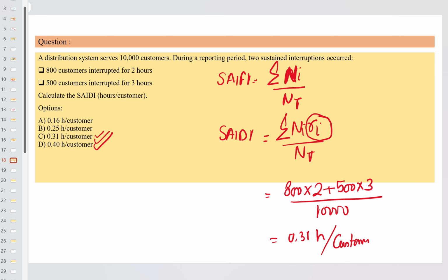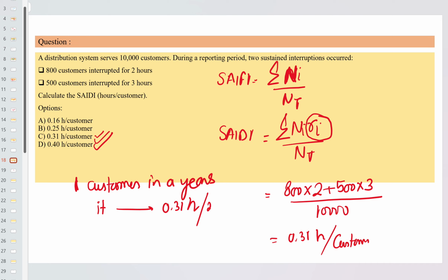So for a single customer in a year, it got an interruption of 0.31 hour out of 24 hours per day, multiplied by 365 days in a year. So this kind of quantification was there, where the time frame is also added, which is more important. SAIDI is a more realistic way to see this compared to SAIFI.